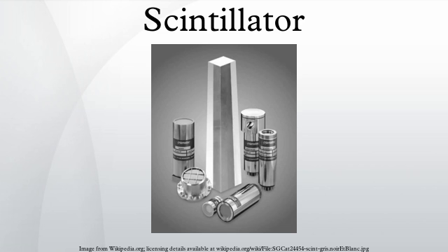CsI, undoped cesium iodide, emits predominantly at 315 nm, is only slightly hygroscopic, and has a very short decay time, making it suitable for fast timing applications. The light output is quite low, however, and very sensitive to variations in temperature.